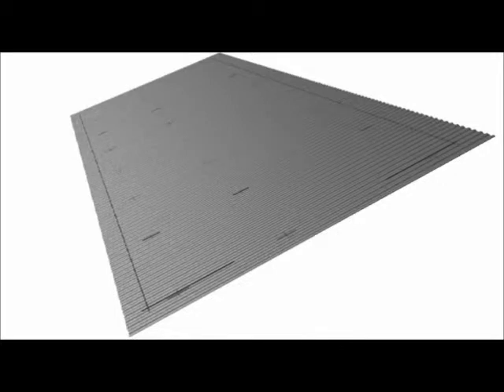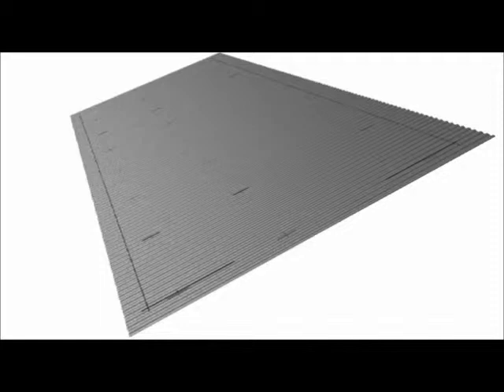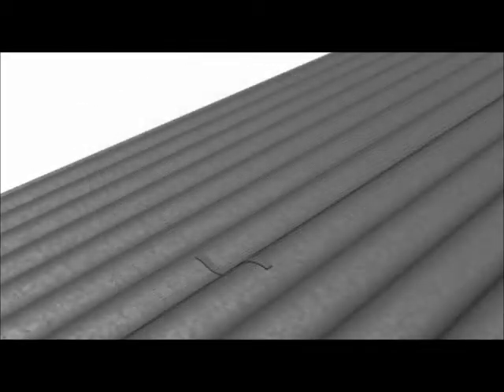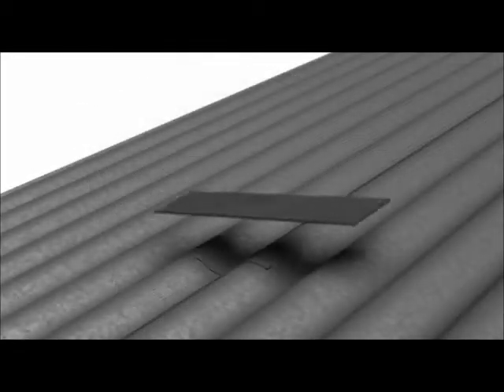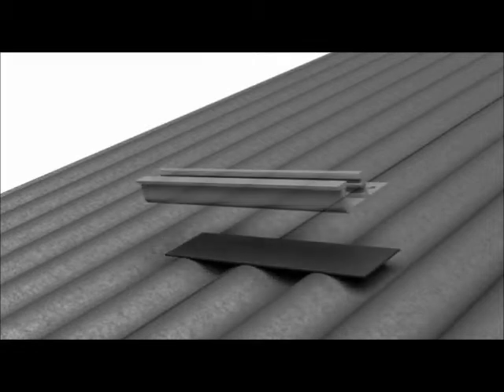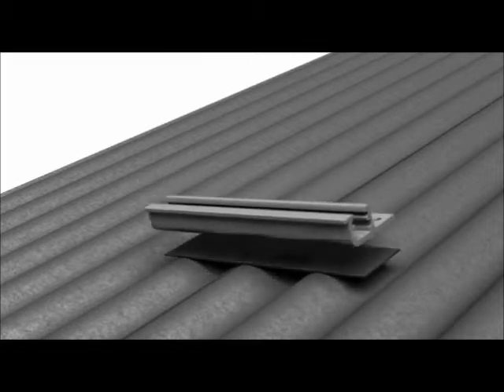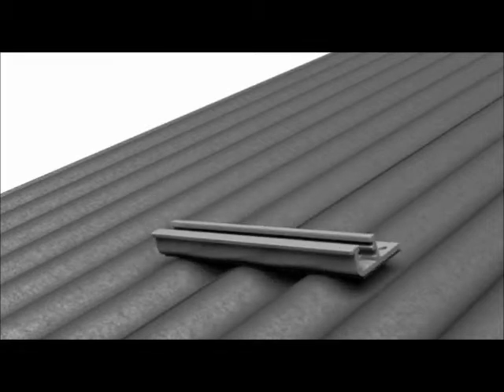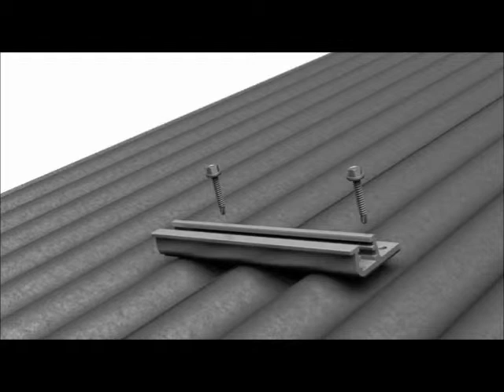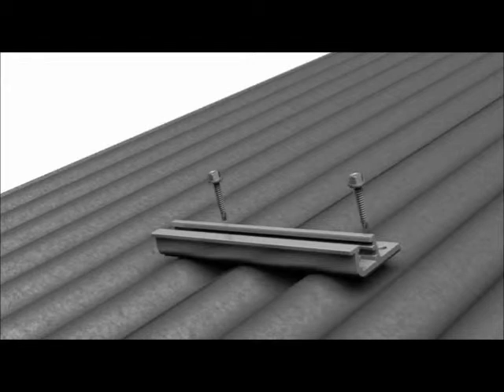Then the first Bigfoot is secured to the roof at the lower, left-most location. To install a Bigfoot, a layer of EPDM rubber is placed between the Bigfoot and the metal roof surface. This acts as a waterproofing layer and for galvanic isolation. With the flange of the Bigfoot facing up-roof, two self-tapping sealing screws are aligned with the screw holes and the ridges of the roofing at opposite ends of the Bigfoot and screwed through into the roof battens.